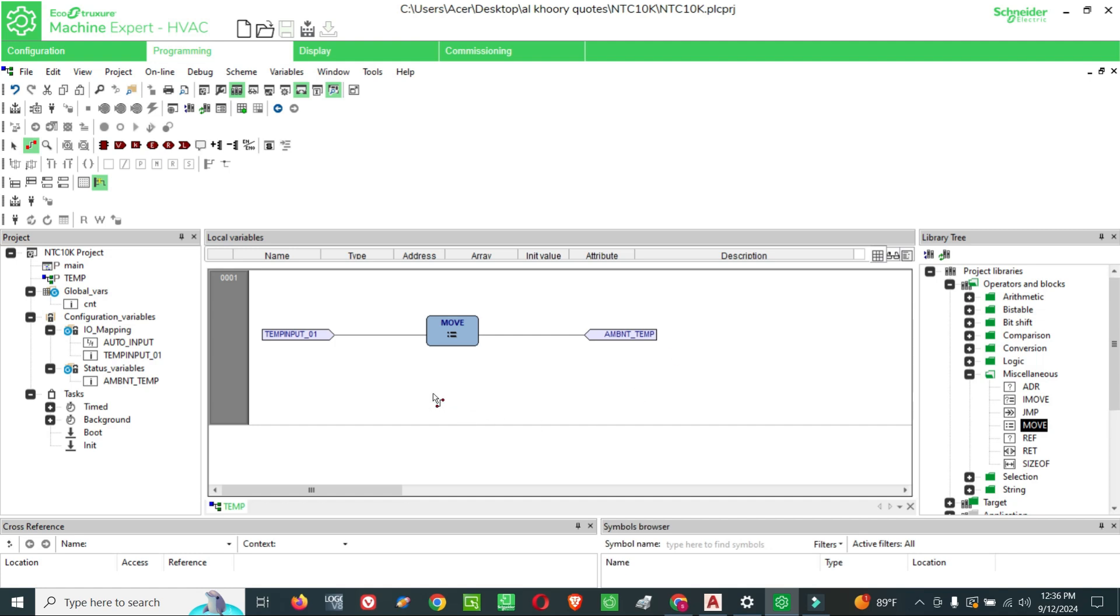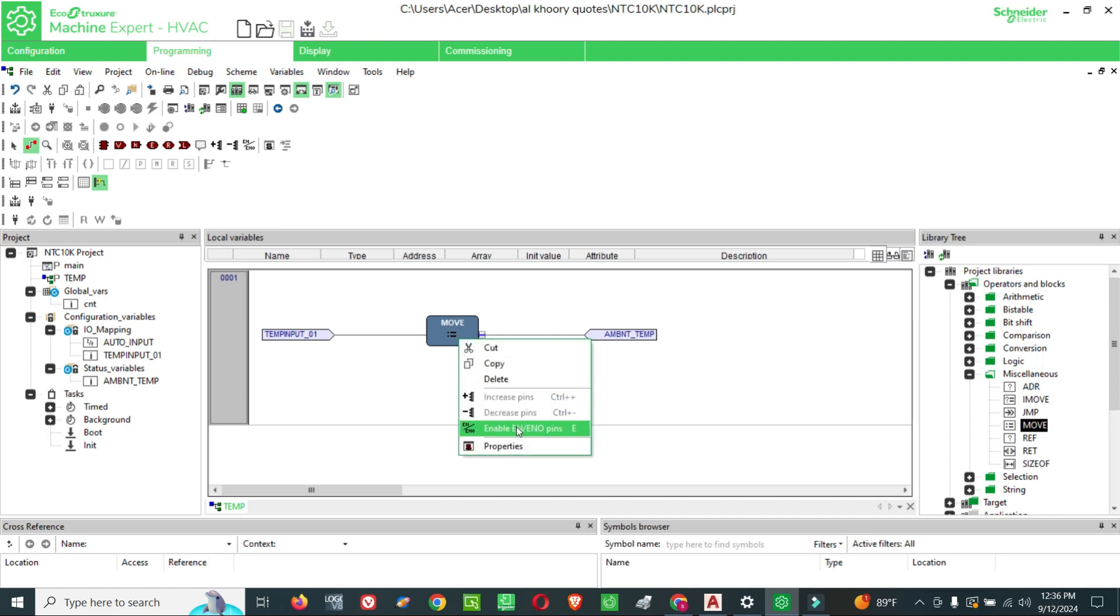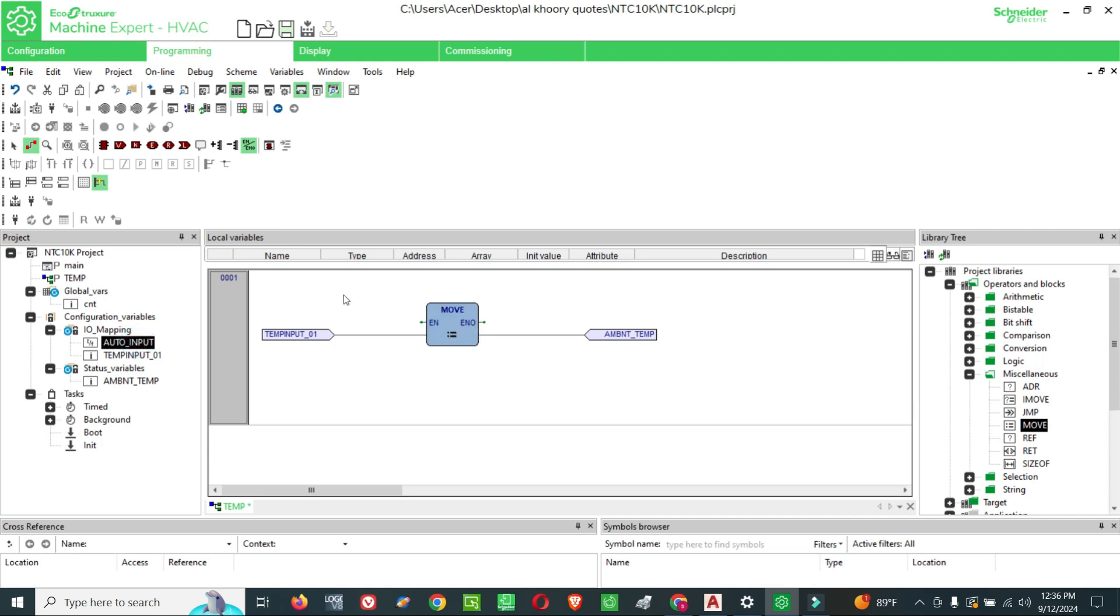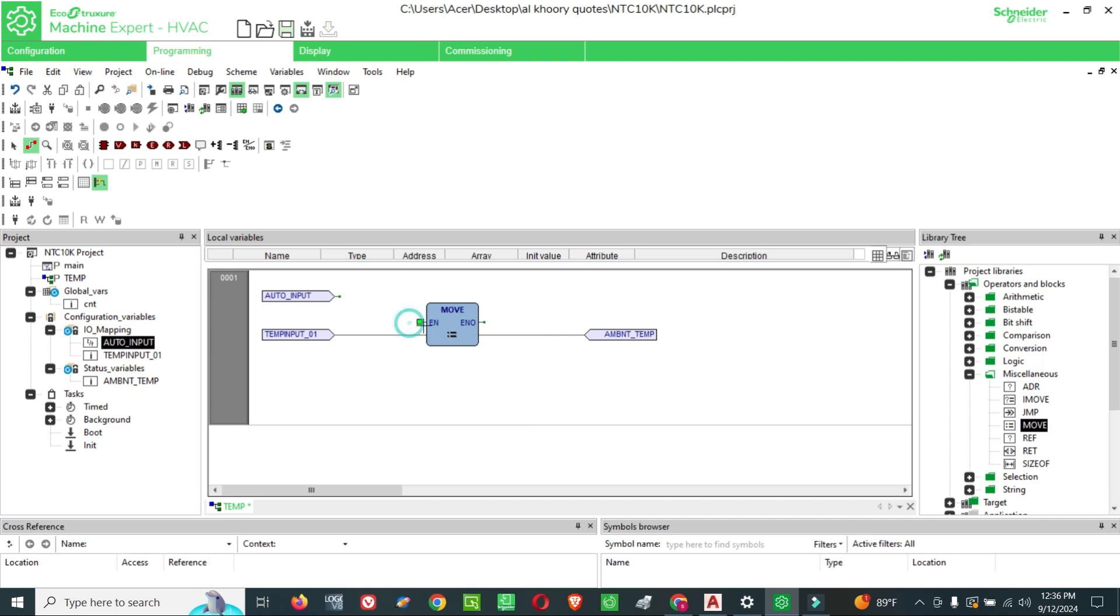Now I want to control this move block. Whenever I want to put my switch on auto mode, then it should show the value. For that we will put an enable pin. With the enable pin we will put one digital input like auto. In this case, when you enable this auto it will show the value, but once you disable it, the last value will remain. For that, we need to do some more logic.